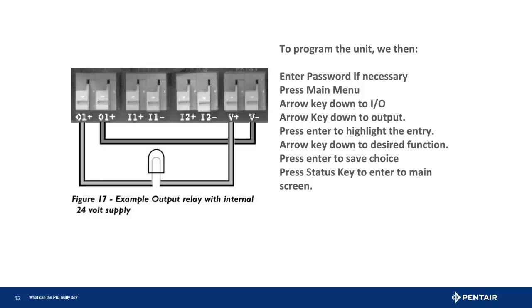Programming, as you see here, is the same pathway used to program the input we stepped through earlier. Enter the password if needed. Press the menu key and arrow key up or down to the I/O menu and hit enter. Scroll till output is displayed and hit enter. Now again, what do you want to know about the drive? Run or fault? And this controls the relay closing, allowing the voltage to pass and energize something. A light, a buzzer, or maybe a magnetic or pump relay.